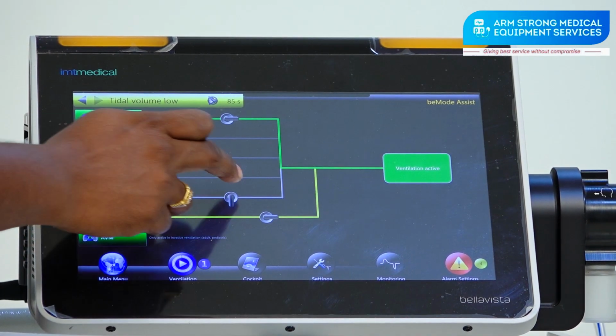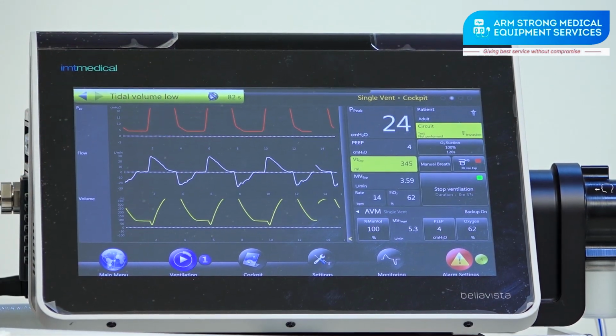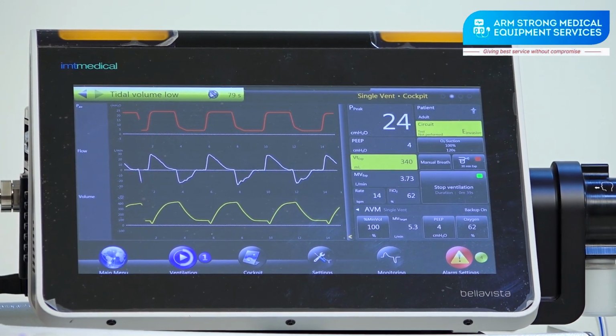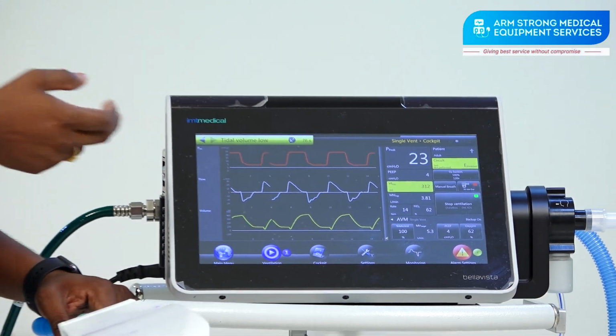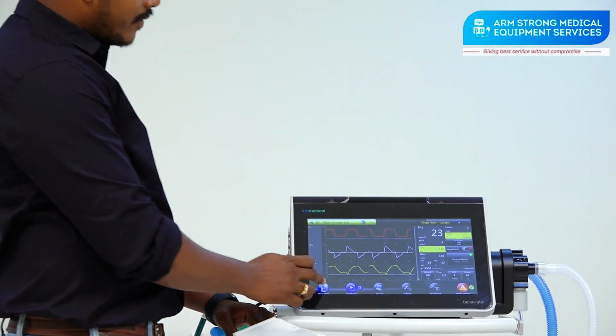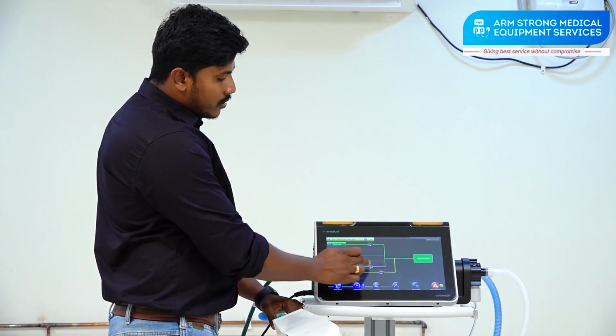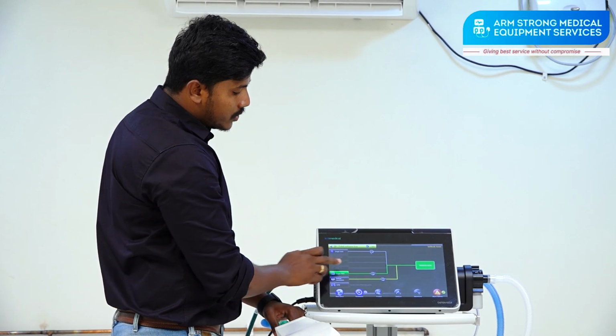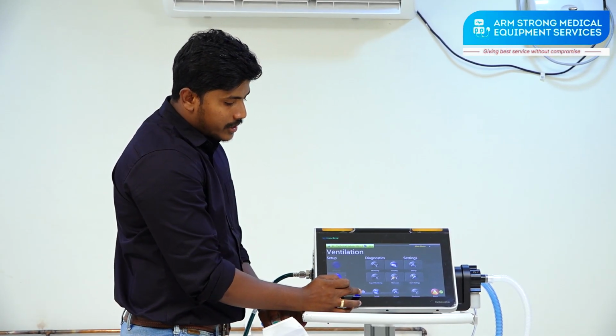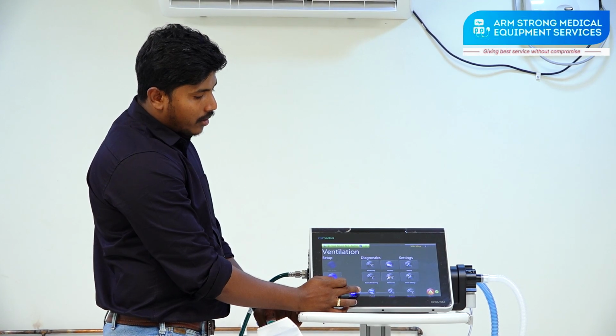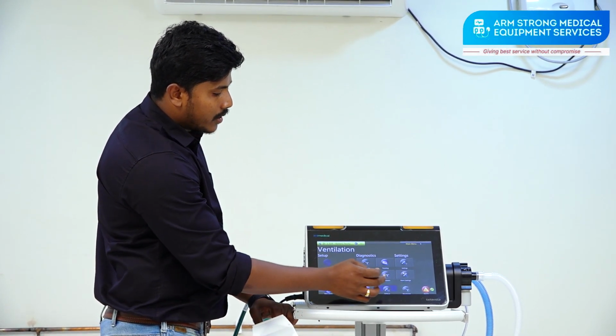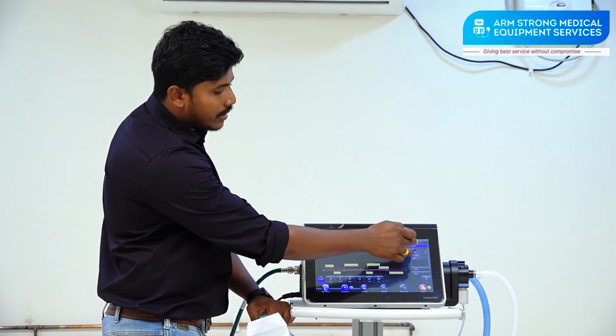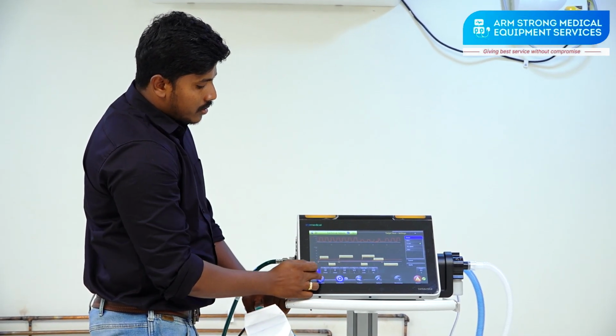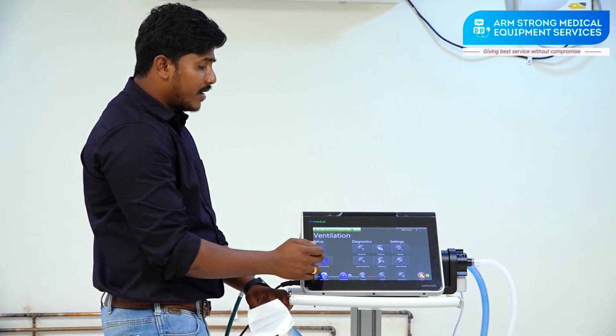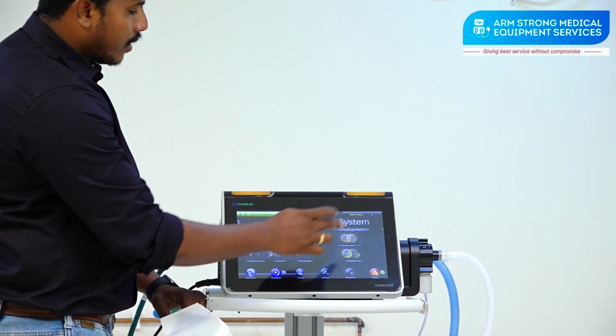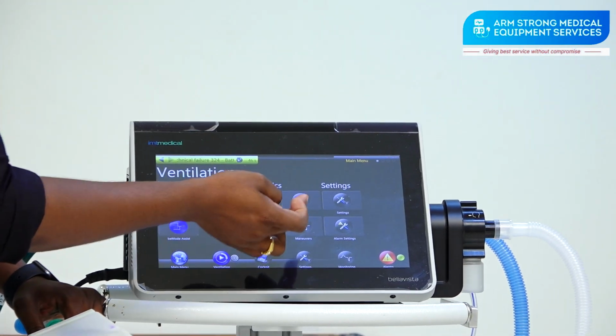And we have a target vent also. In a lot of other ventilators also, like Maquet, GE, all these ventilators, we have a technology called volume guarantee. On this ventilator they have given target vent. So the target vent option is separate. If you switch on the target vent, see here the symbol also changed. In target vent we have ventilation modes. See, in target vent we have these 4. This is like a volume guarantee only. In target vent we have monitoring of this.